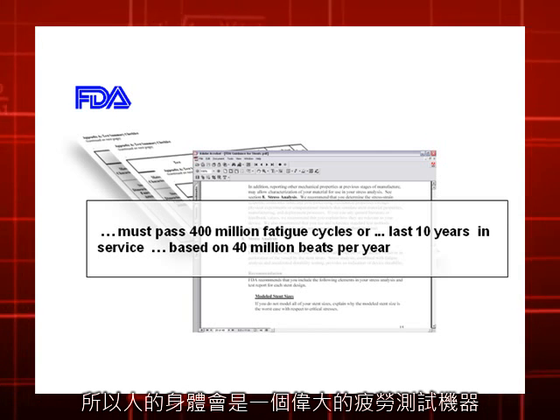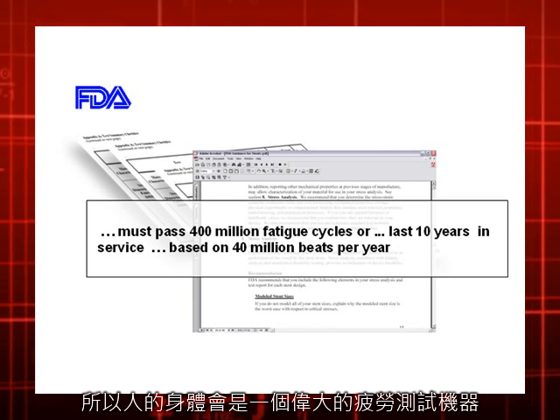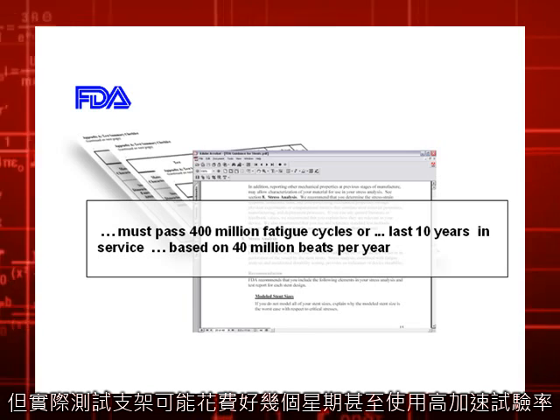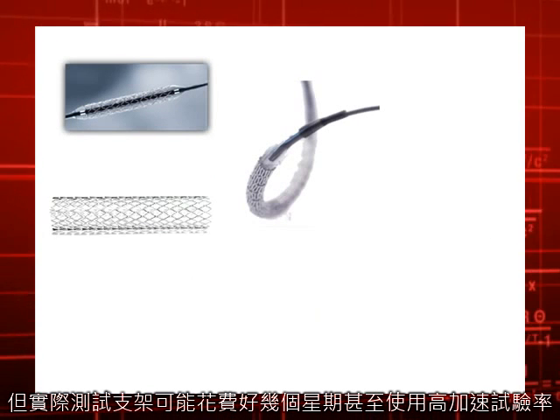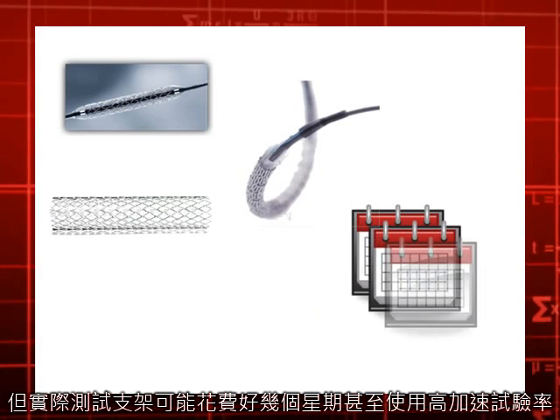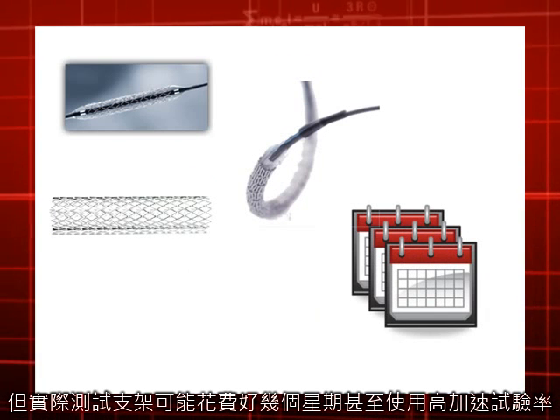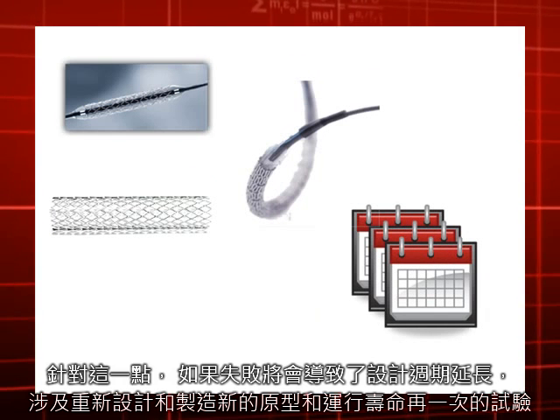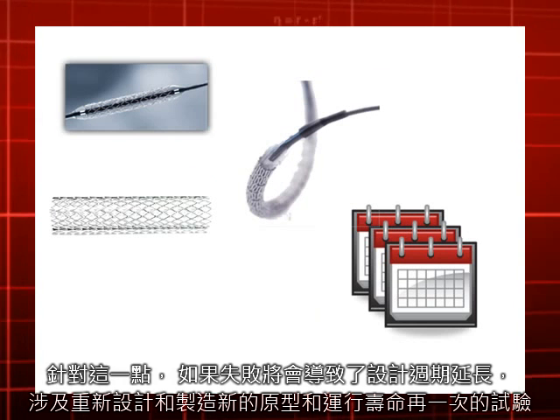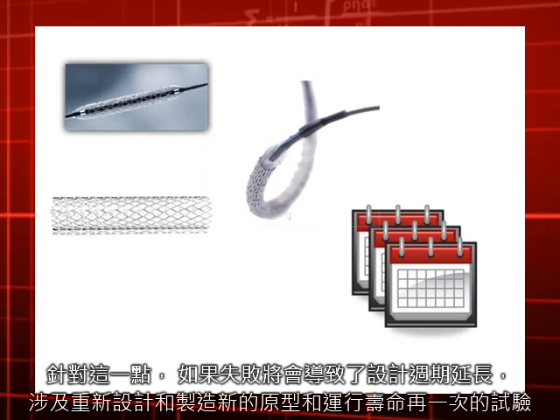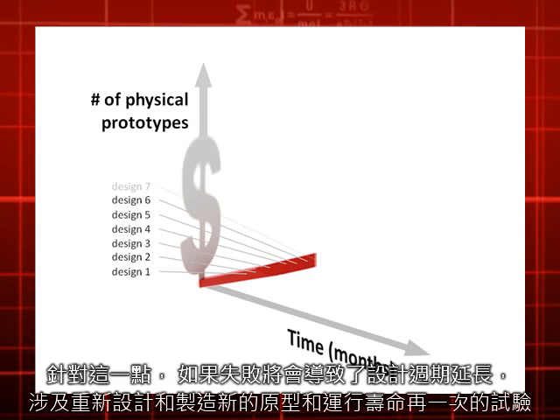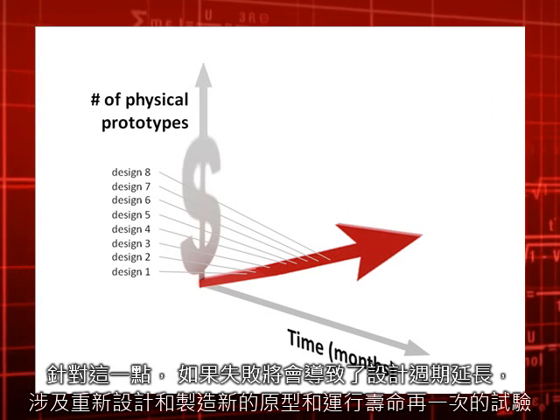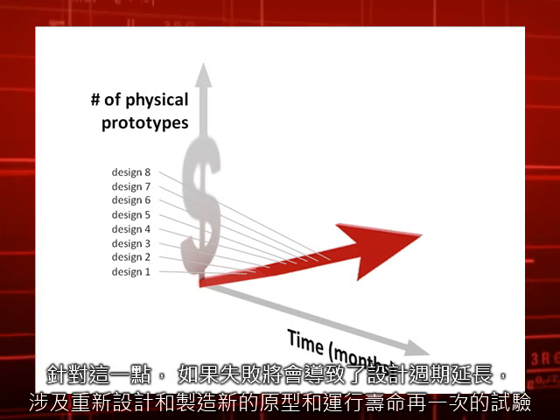So your body is a great fatigue testing machine. But physically testing stents can take many weeks, even if you use highly accelerated testing rates. And at that point, if the design fails, it leads to a prolonged design cycle involving a redesign and creation of new prototypes and running the life testing over again.